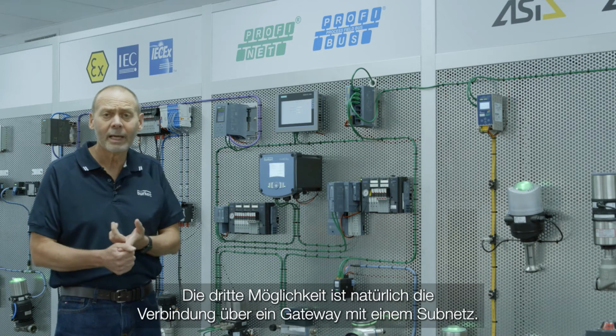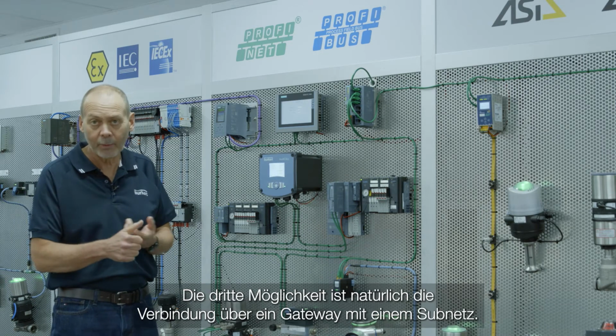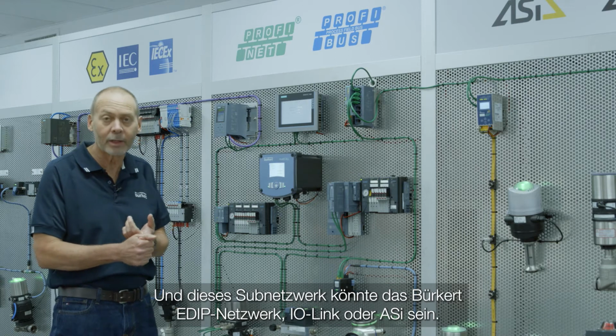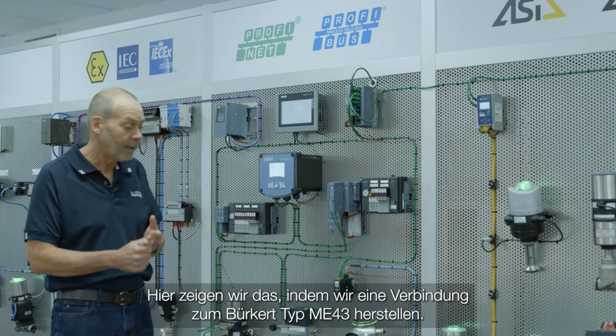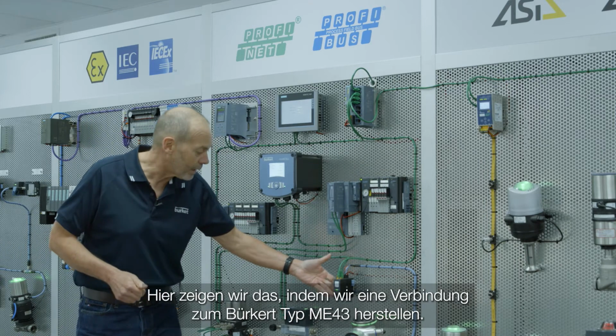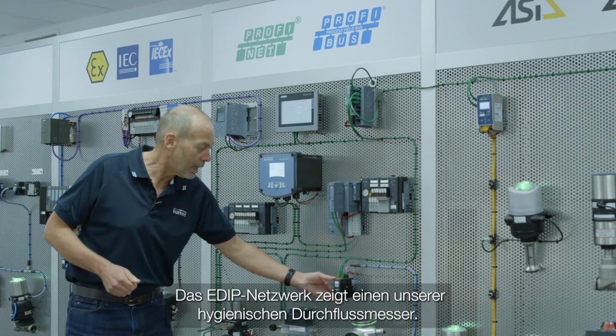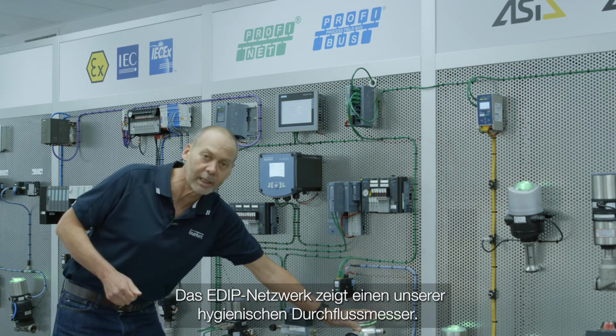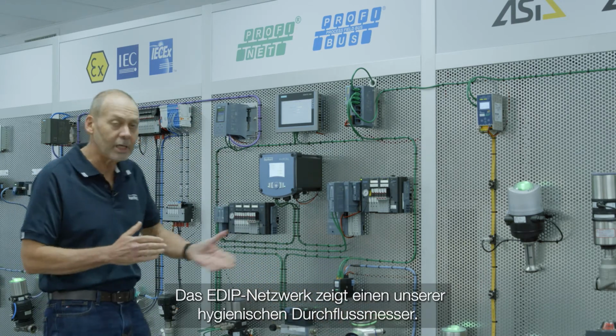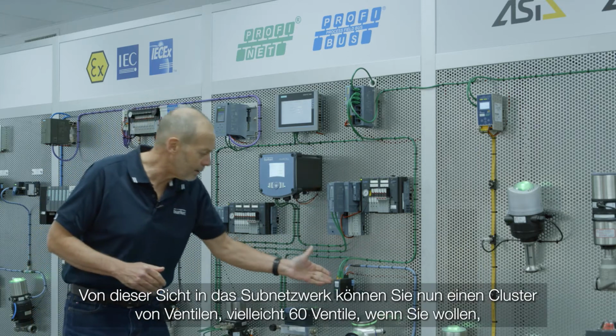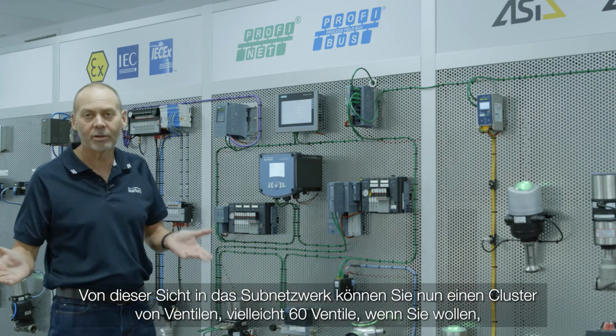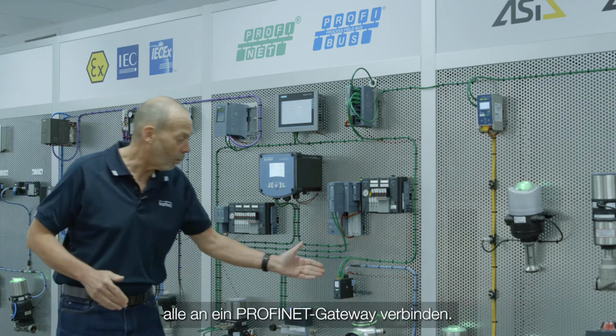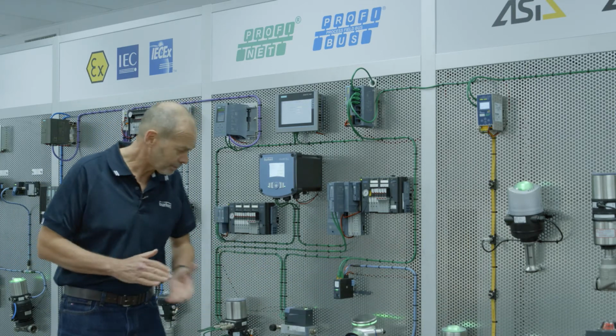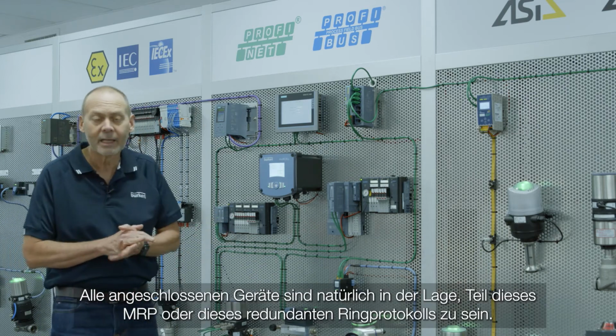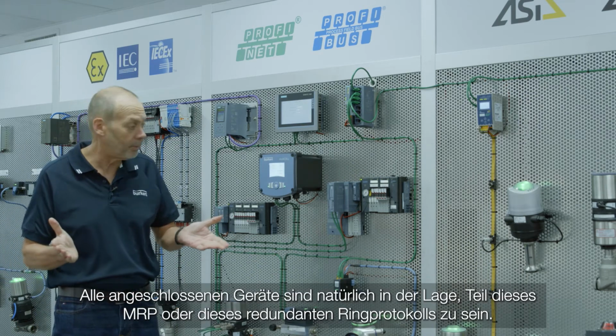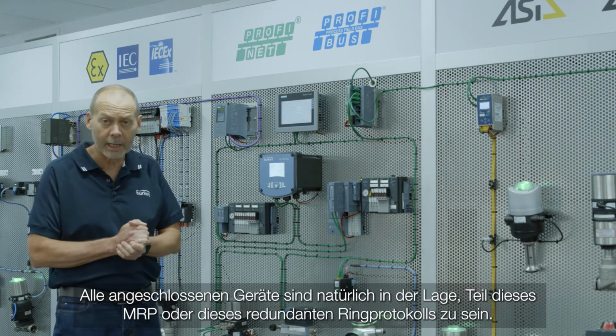The third way, of course, is when we connect via a gateway to a sub-network, and this sub-network could be the Bürkert EDIP network, it could be IO-Link, or it could be ASi. In this instance, we're showcasing that by connecting to the Bürkert ME43 and then breaking into the EDIP network, where we're showcasing one of our hygienic flow meters. From that sub-network, you could put a cluster of valves, maybe 60 valves if you like, all on one PROFINET node. All of these devices that are connected are capable of being part of that MRP, or redundant ring protocol.